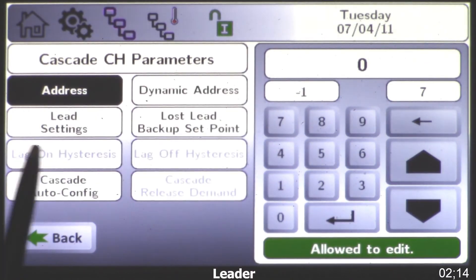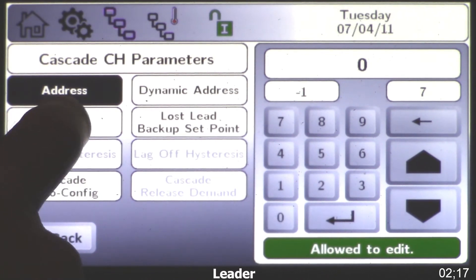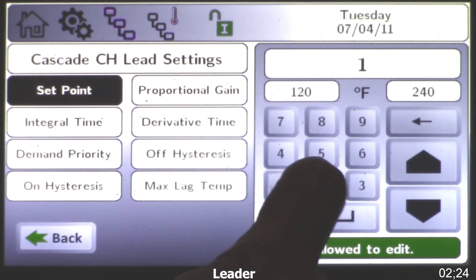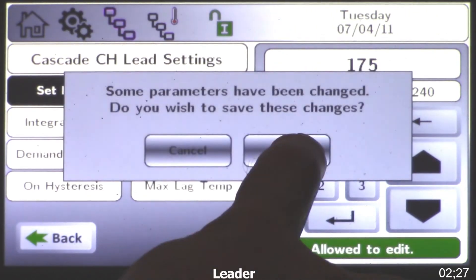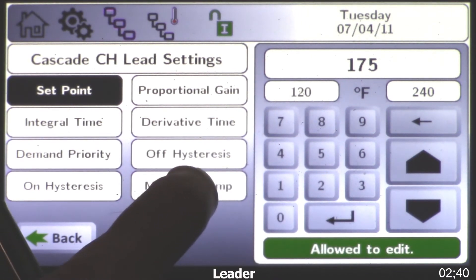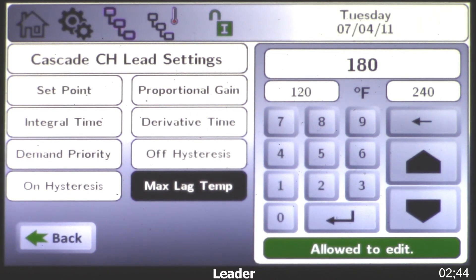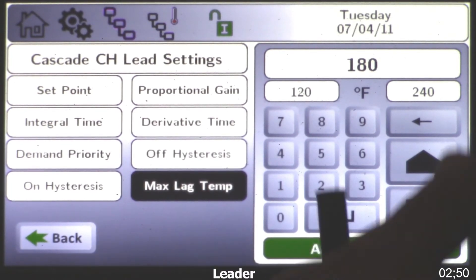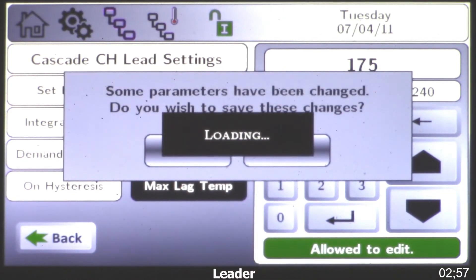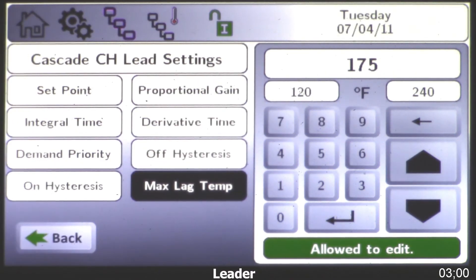I'm going to click lead settings and now I can get into a setpoint — in my example I'll say 175, then click enter. Under here you've also got your off hysteresis and on differentials for your setpoint at the system sensor. I also want to choose a max lag temperature — we used the 170 setpoint for the member or lag boilers if we lose the leader, so here I'll type in 175. Now I'll come back to the home screen.